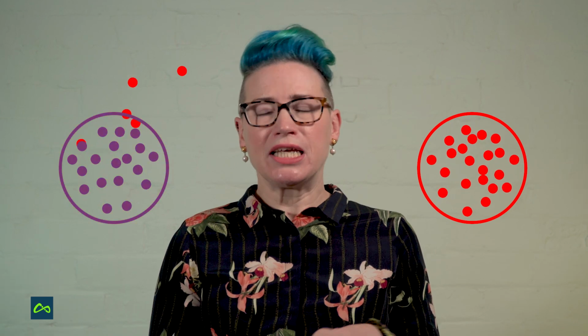So how do we make use of that available energy? The heat pump uses refrigerant which boils at a very low temperature, and it's important to remember that generally energy or heat moves from hot to cold. As long as the refrigerant gas is colder than the source, which is your air or your water, you will be able to extract and move the energy from the hot source, which is the air, to the cold source. That sounds odd because air at minus 5 doesn't sound hot, but in terms of refrigerant temperatures, that is hot. And again, remember that there's energy available right down to minus 273 degrees.